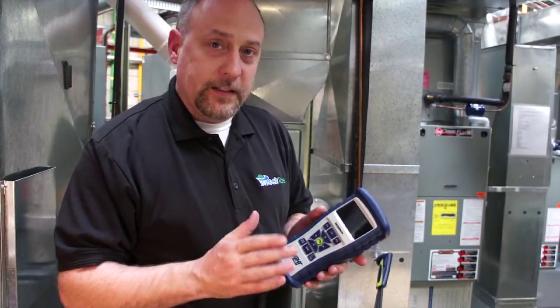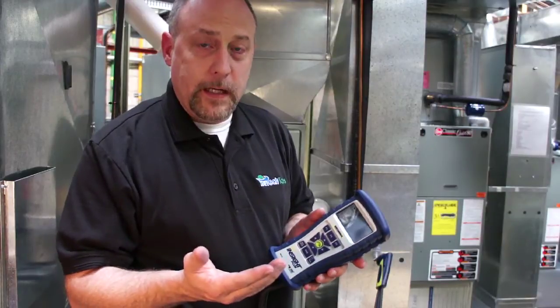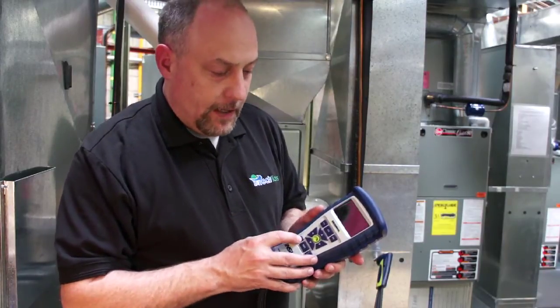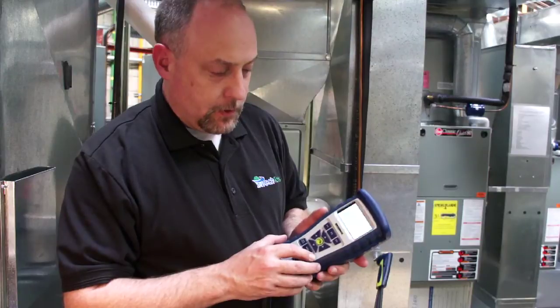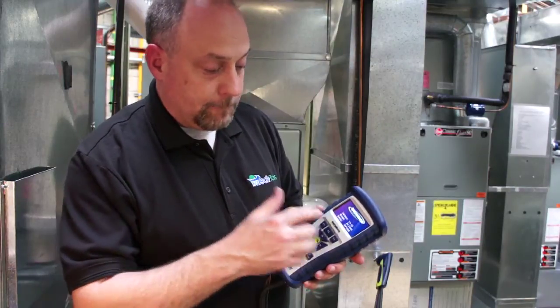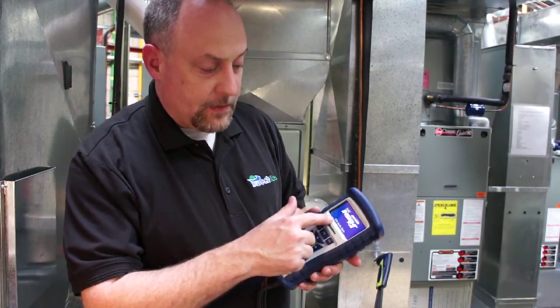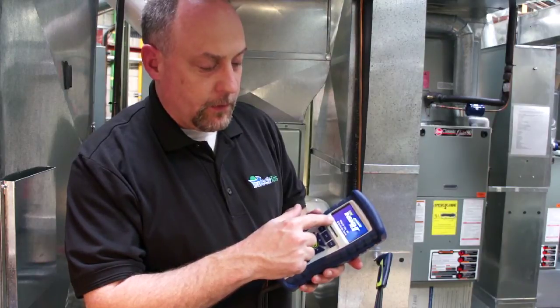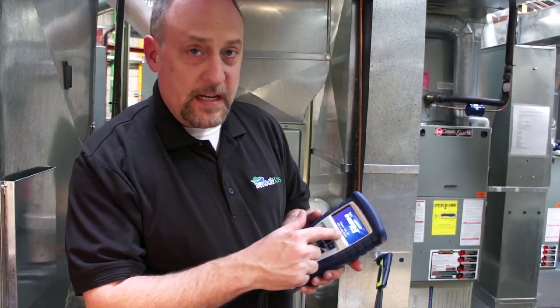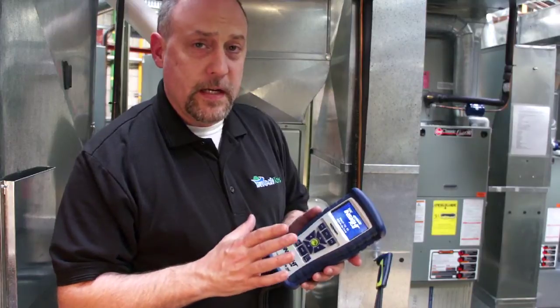And if we don't plug it in, it's going to go through a full minute of warming up when we do that. If we turn it on now, we're going to push the power key. It's going to go through its countdown, so it's bringing up the menu and the software version, and then it's saying warm up 58 seconds, but we're not going to go completely through that 58-second period.